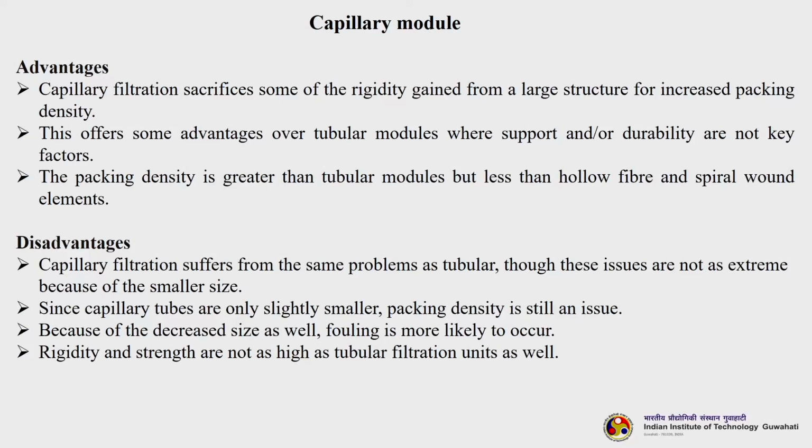Since capillary tubes are only slightly smaller, packing density is still an issue. Because of the decreased size as well, fouling is more likely to occur, and rigidity and strength are not as high as tubular filtration units, because since they are self supporting and do not have any external support, the mechanical strength is an issue.